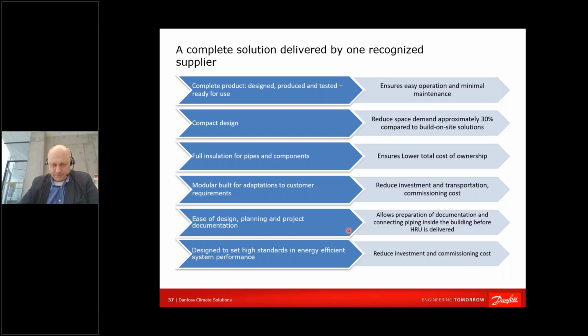It's easy to design. Pipes of a heat recovery unit are always in the same order. Supply to the building and recovery pipes. So that's quite simple. You can just design pipes which should come to the certain place, and you can wait until the heat recovery unit will be delivered for the installation. So you can work simultaneously. You shouldn't wait for something. Yes, and it's designed to set the high standards on energy efficiency.